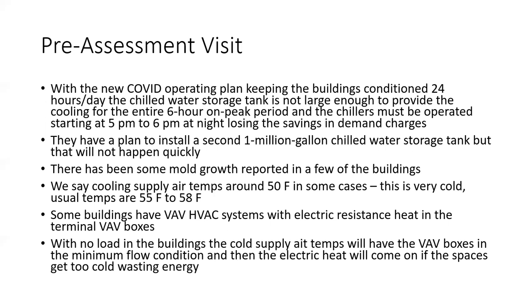A lot of these buildings are what we call VAV, variable air volume buildings. And so the HVAC system has VFDs on the fans. And these people have VFDs on everything. It's amazing. I've never seen a place that had so many VFDs in my life. We saw some air handlers that had VFDs on the supply fan. And what happens is you distribute out to these, they call them VAV boxes, that actually control the airflow to particular offices or spaces or conference rooms or whatever.